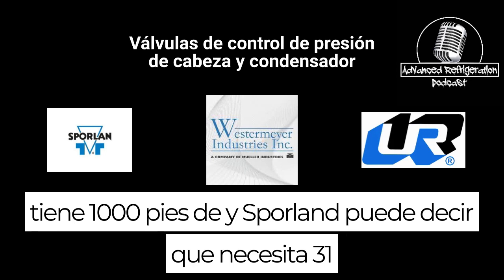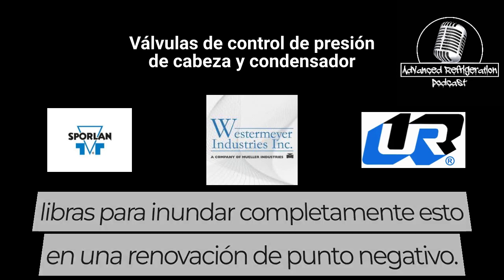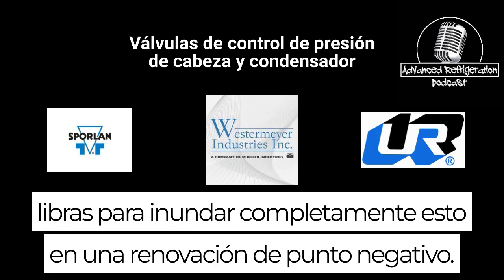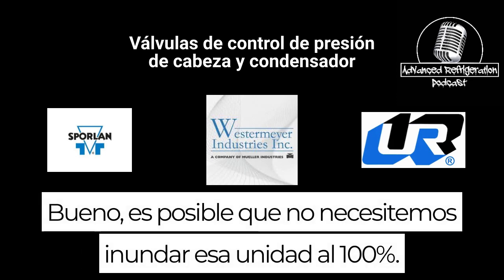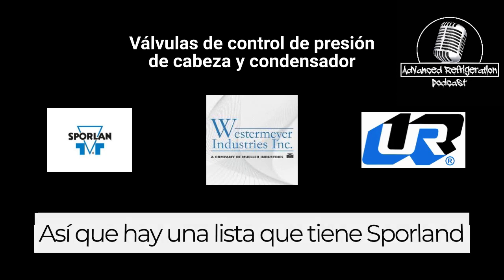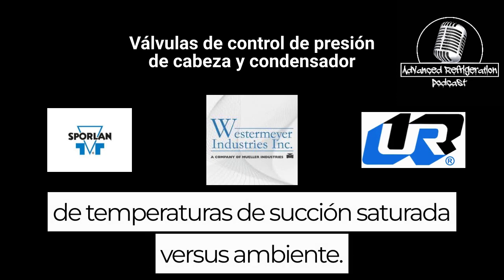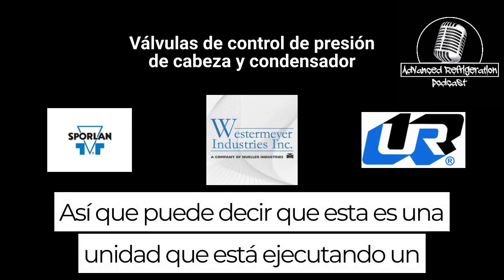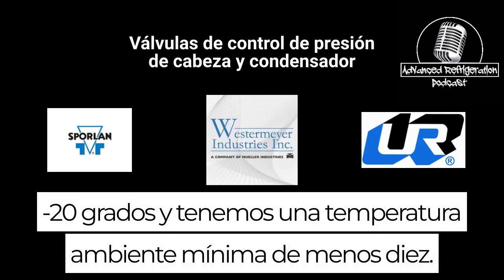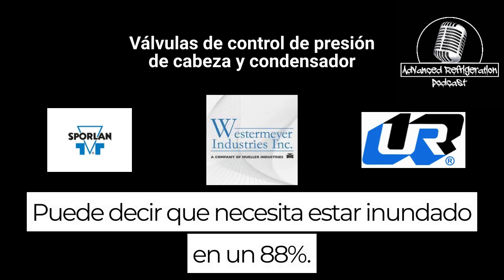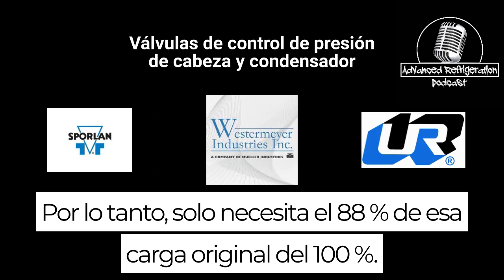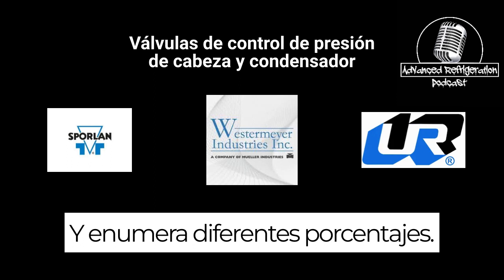And Sporlan may say you need 31 pounds to completely flood this at a minus 20 degree ambient per condenser. Well, we may not need to flood that condenser 100%. So there's a list Sporlan has of saturated suction temperatures versus ambient. So it may say this is a unit running a minus 20 degree evaporator and we're running a minus 10 minimum ambient. It may say you need to be flooded 88%. So you only need 88% of that original 100% charge. And it lists different percentages.